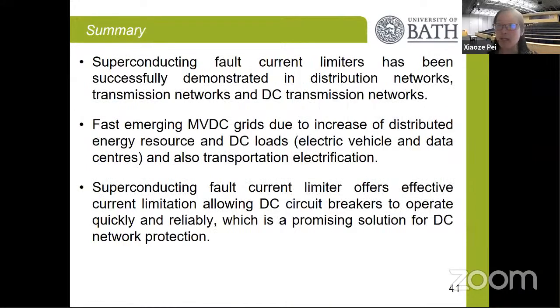So this brings me to the summary of my talk today. We can see that the superconducting fault current limiter has been successfully demonstrated for the distribution network, transmission network, and the DC transmission network. Secondly, there is a very fast emerging market for the MVDC grid for the integration of renewable generation and DC loads, and also for transportation electrification. That is why our research group is mainly focused on DC network protection. We believe the superconducting fault current limiter can offer very effective fault current limitation, so that it allows the design of the DC circuit breaker to operate quickly and reliably. And we think this is a very promising solution for DC network protection.